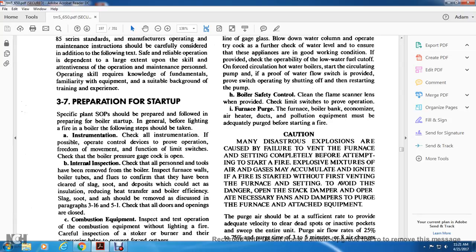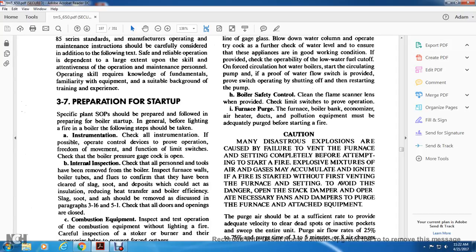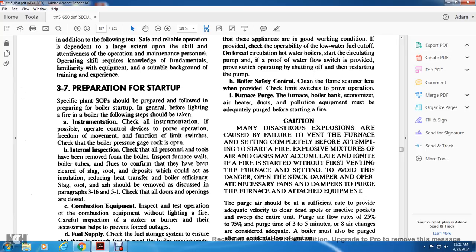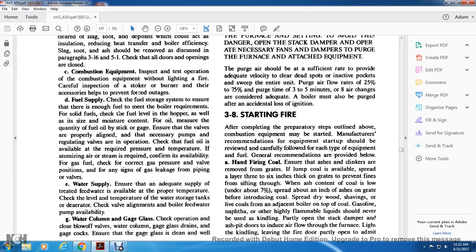3-7 Preparation for start-up. Specific standard operating procedures should be prepared and followed when preparing the boiler. Before lighting any fire in the boiler, the following setup should be made and checked: all instrumentation controls, operating control devices should be checked for proper operation, freedom of movement, and function with limit switches. Check the boiler pressure gauge cock is open. Internal inspection: check all personnel tools have been removed from the boiler.